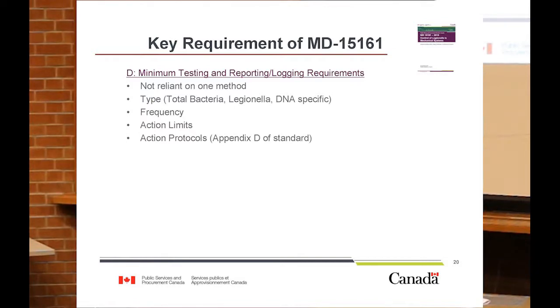That brings me to the last key requirement of the standard, which is associated with our minimum bacterial testing. We're not reliant on one method at PSPC. We use 3 different types of testing to look at total bacteria, general bacteria, not Legionella specific, as well as DNA specific for Legionella. And we've established minimum frequencies, action limits, and action protocols for those testing results.